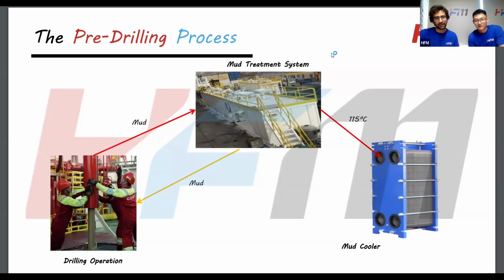So basically we have different answers. The majority said it's because impurities can accumulate inside the heat exchanger, and this answer is correct. The point is that when the mud is pumped out of the soil, it brings with it rock particles, sand, and stuff like that. This can accumulate inside the heat exchanger, and when it accumulates, it affects the efficiency and working life of the heat exchanger, because the heat exchange itself is going to reduce the temperature of the fluid.